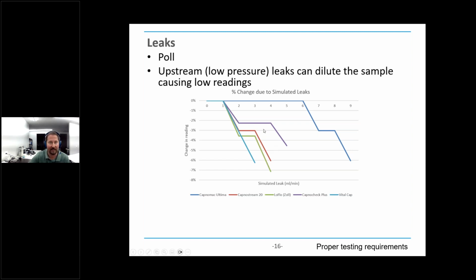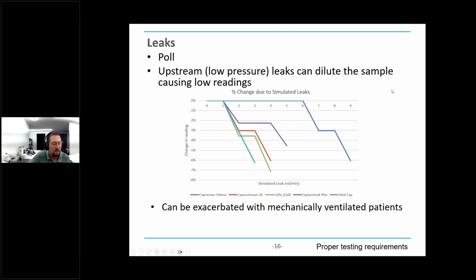The low flow devices, the ones with 30 to 50 milliliter per minute flow rates, are really susceptible to these leaks. This one on the right over here is actually an anesthesia device. It has a 200 milliliter per minute sample rate. And so these little leaks don't affect it nearly as much because it's such a large flow rate, but for these other ones, it's important to check for. The other thing to realize is that leaks can be exacerbated when a patient's on a mechanical ventilator. The additional pressure the ventilator puts on the system can make those leaks worse. A lot of people don't realize that. So you really should be doing a full leak check on your devices every time because it is important.